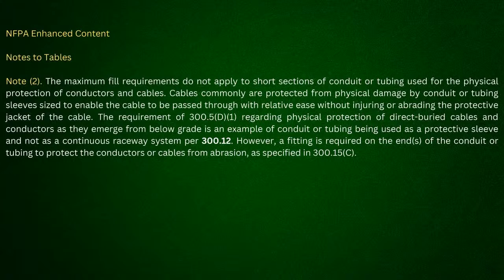And then like Tabitha was saying, when you look at (B), it says adjustment factors shall not apply to conductors in raceways having a length not exceeding 24 inches. And in other words, what they're telling you there is that's where it's connected from end to end. So if you've got a nipple which is 24 inches or less, that's connected end to end. You don't apply any adjustment factors. Anything over 24 inches, that's a raceway that connects at both ends per Note 2 of Chapter 9, Table 1. Then you have to apply them.